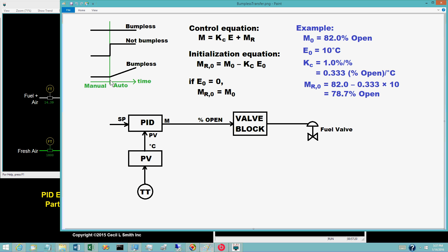The third possibility is an intermediate. The controller output is constant prior to the switch to auto, but immediately following the switch, the controller output begins to increase or decrease. No abrupt change occurs at the instant of the switch, so the transition is bumpless. For a PID block, this behavior occurs when the controller is switched to auto with a setpoint that is not equal to the PV.